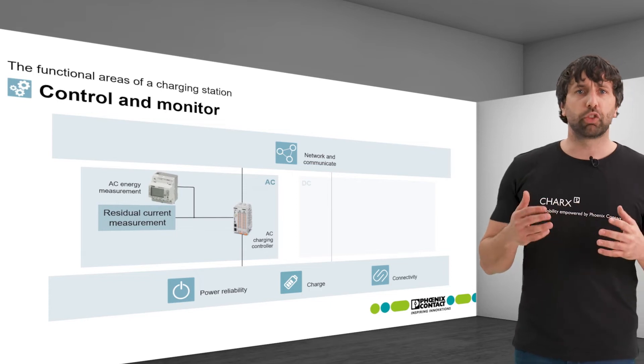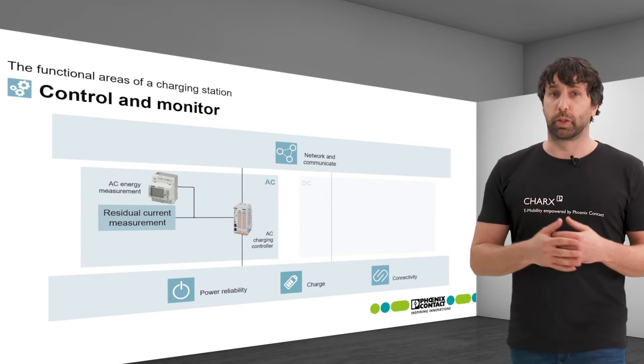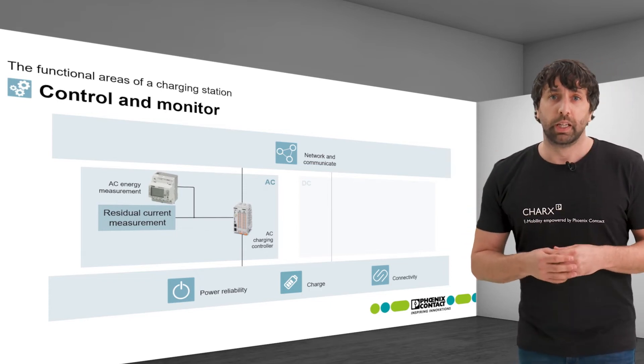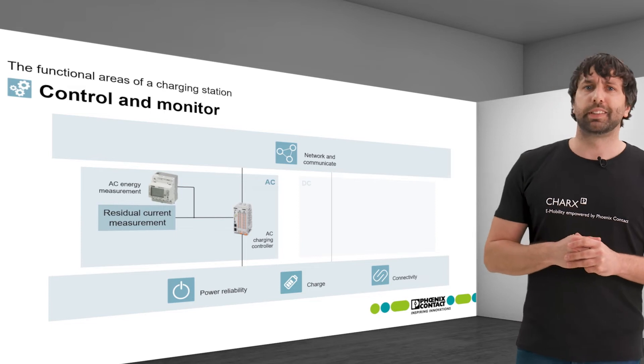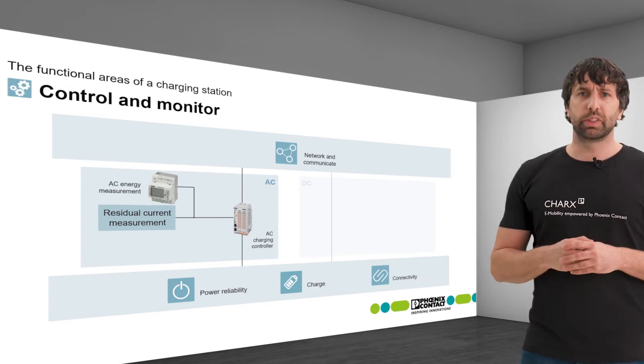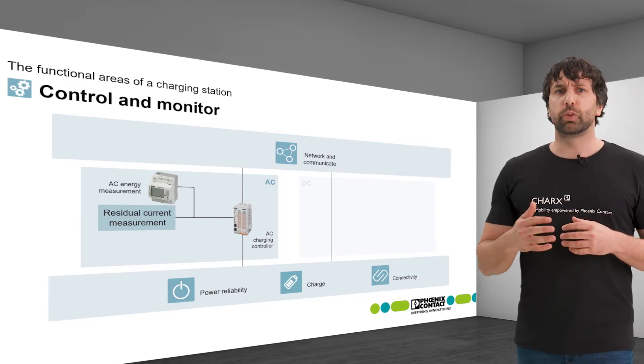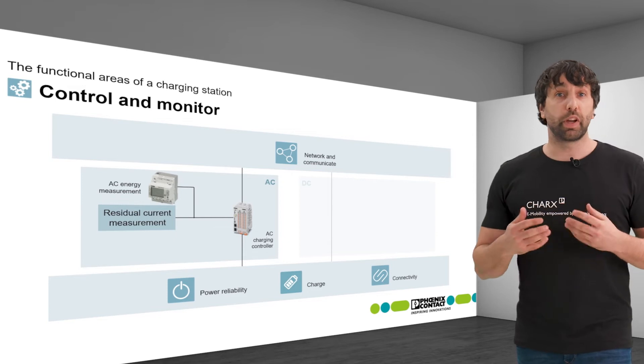A much less expensive alternative is a type A circuit breaker. Since it detects only AC residual currents, it must be combined with a DC residual current measurement.